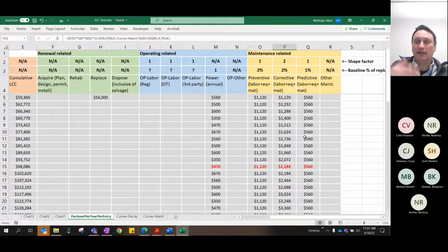However, again, like I mentioned a little bit in the beginning, I would like to caution you, the same pump installed in different locations may actually be trending, and they may have a slightly different baseline as well. If you have actual data, the idea would be to correct it with actual data. If you don't have actual data, I think it's as good as it gets and a relatively safe assumption to come up with an asset class applicable number to use, for all the same pumps in all pump stations, for example.